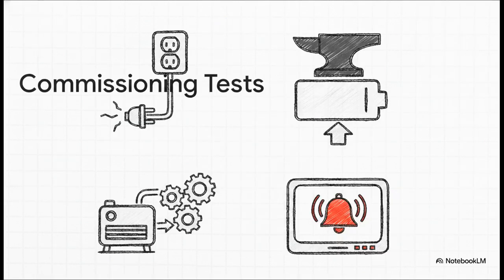A properly commissioned system has to survive a gauntlet of real-world tests. You have to simulate a hard power outage, you've got to bring in massive dummy loads for full load bank testing, just to verify that the battery autonomy is actually as long as your math says it is. You have to test the sequential loading of the generator and ensure the medical IT fault alarms perfectly link back to the central monitoring system. Every single component must be pushed to its absolute limit, exactly as guidelines like the UK NHS mandate.